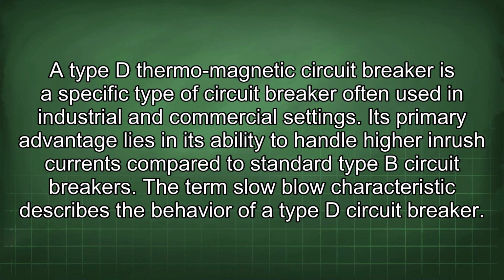Type D thermomagnetic circuit breaker is a specific type of circuit breaker often used in industrial and commercial settings. Its primary advantage lies in its ability to handle higher inrush currents compared to standard Type B circuit breakers. The term slow blow characteristic describes the behavior of a Type D circuit breaker.